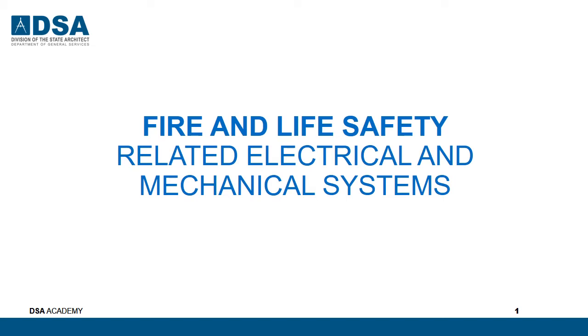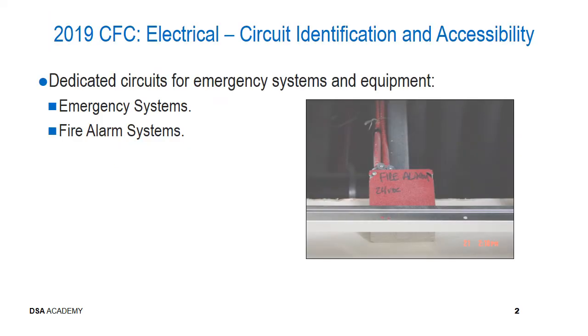Let's move in to those mechanical and electrical systems that are fire and life safety related. For fire alarm devices, circuit identification and accessibility is required. Dedicated circuits for emergency systems and equipment include all emergency systems such as lighting and fire alarm systems. A common misconception is that conduits and boxes must be red in color. The code states that wherever there is a fire alarm junction box, it shall be identified as fire alarm.